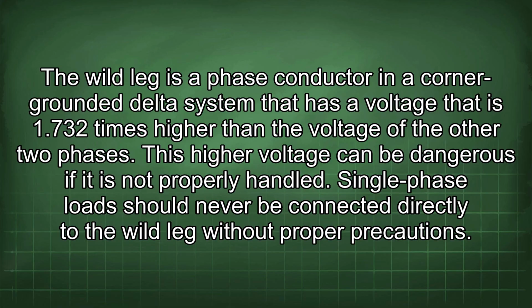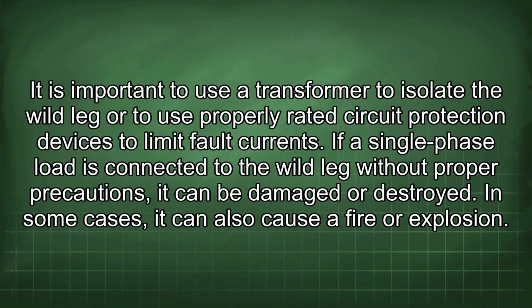This high voltage can be dangerous if it is not properly handled. Single-phase load should never be connected directly to the wild leg without proper precautions. It is important to use a transformer to isolate the wild leg or to use properly rated circuit protection devices to limit fault currents.